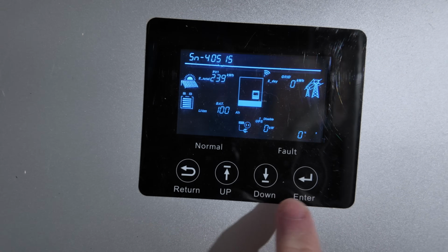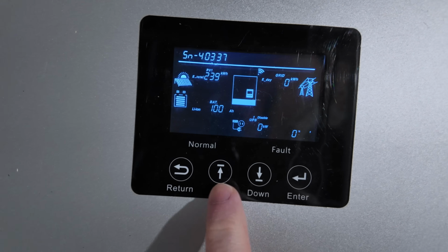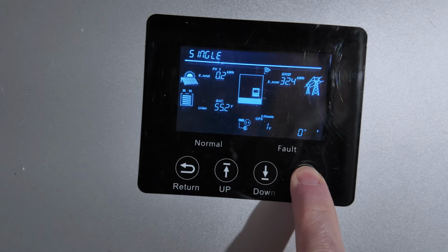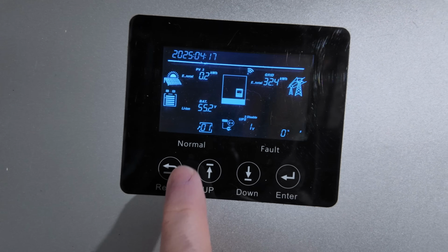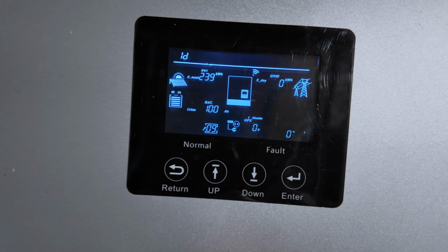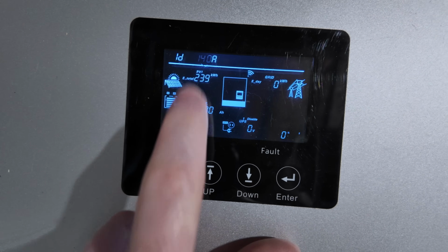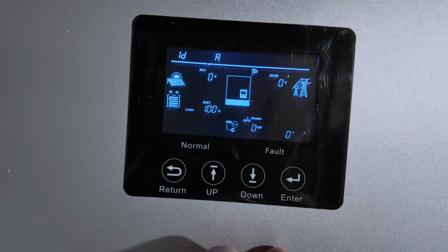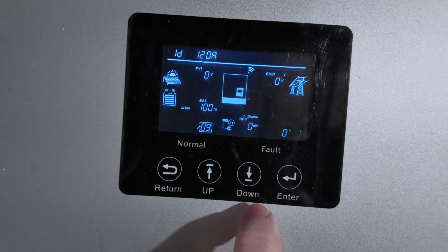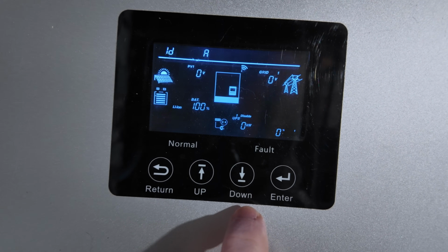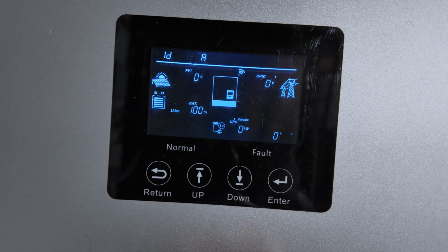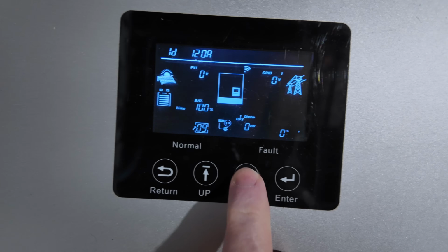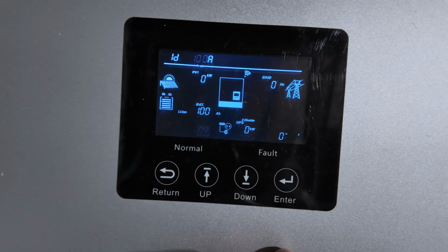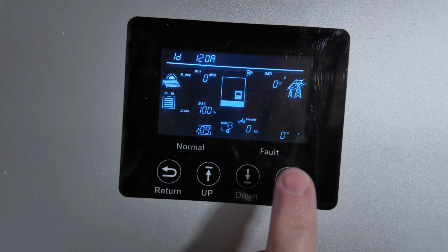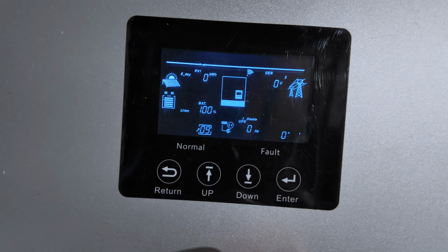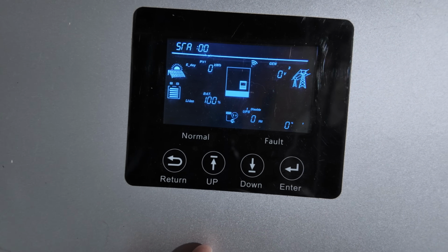One other thing you need to do with this specific battery, if you're using it on the 6000 XP, is go back into the settings. You need to limit the current, which is option 9, and by default it's 140 amps. I believe these Degson connectors can only handle up to 120, so if you're putting multiples in parallel, have it at 120. If you're doing one battery, do 100 amps. Then you would hit enter and back out.